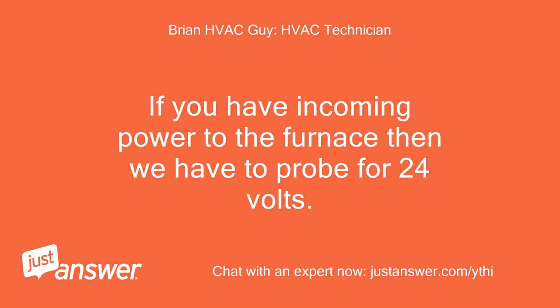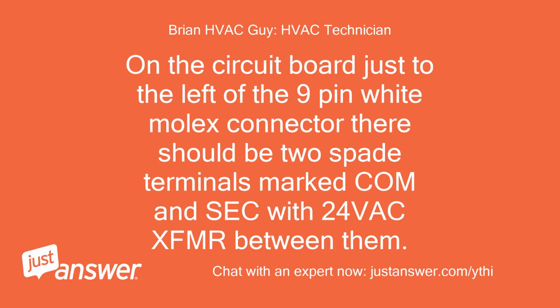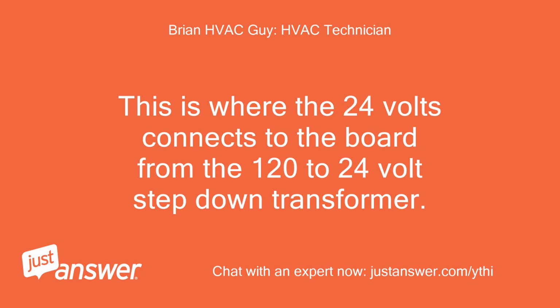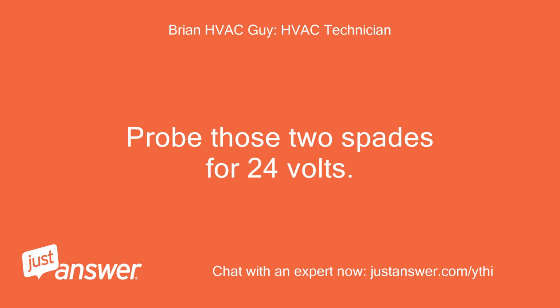If you have incoming power to the furnace, then we have to probe for 24 volts. On the circuit board just to the left of the 9-pin white Molex connector, there should be 2 spade terminals marked COM and SEC with 24 VAC XFMR between them. This is where the 24 volts connects to the board from the 120 to 24 volt step-down transformer. Probe those two spades for 24 volts.